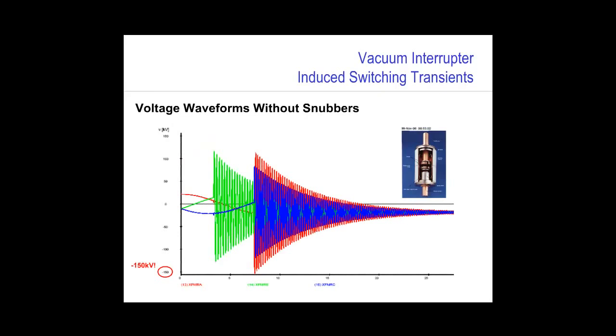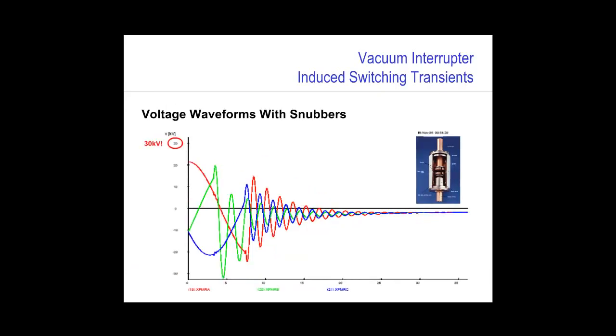Of course, when switching into a purely inductive load, for instance a transformer winding, when you drive current to zero, voltage has to go somewhere, and in this case it goes into the sky. As you can see from the voltage waveforms on this same analysis, I have peak voltages of close to 150 kV. In a 90 kV BIL transformer, this is beyond the device's rating, and that's what will drive you towards failure. Fortunately, resolving this application issue is fairly straightforward.